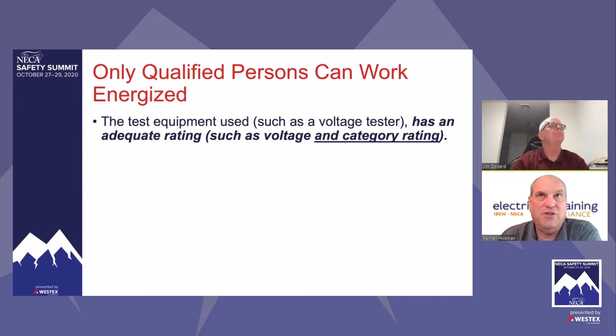So category 4 meters at service equipment, category 3 a little bit further down. But if it doesn't have a category rating, it's sort of like, if you don't know when it's been maintained, has it been maintained? The answer is no. And that's another thing that has to be documented: proficiency when the person uses it, to show that they know how to use the test equipment, including its limitations and including the display.